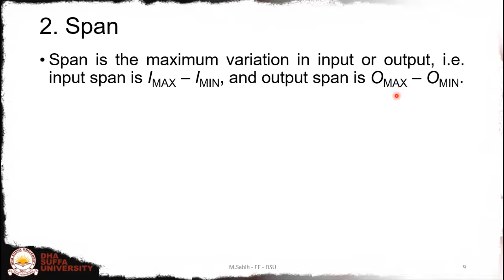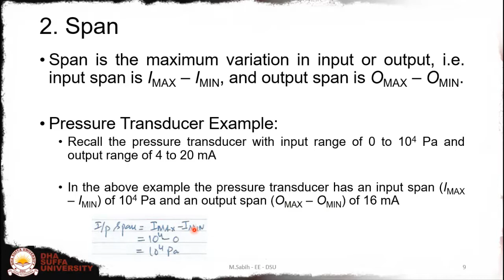An input range from 0 to 10 raised to the power 4 Pascal, and the output range is 4 to 20 milliamps. In the above example, the pressure transducer has an input span of 10 raised to the power 4 minus 0, so you will get 10 raised to the power 4 Pascal. So this is the input span, and the output span is around 16 milliamps, because this is the subtraction 20 minus 4, you will get 16 milliamps. This is how you get the input span, and this is how you are going to get the output span.